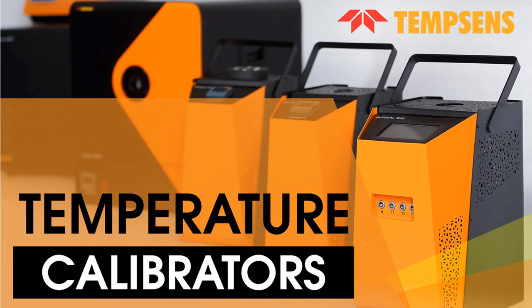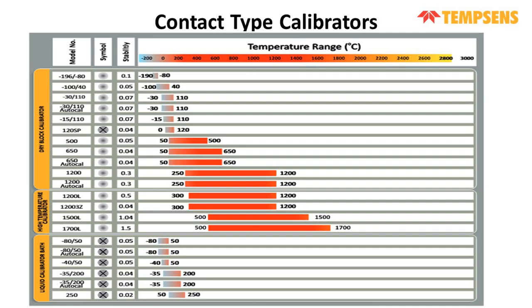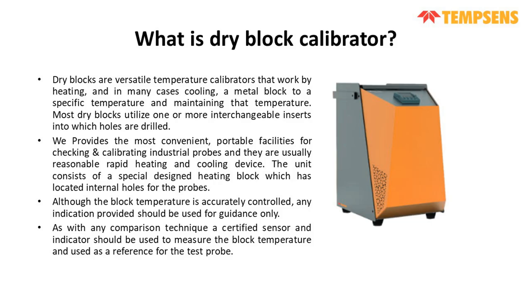Moving ahead with our webinar discussion. Basically, calibrators can be divided into two parts: contact type and non-contact type temperature calibrators. These are the ranges that we have for the dry block, the high temperature calibrator, and the liquid calibration baths. So what is a dry block calibrator?